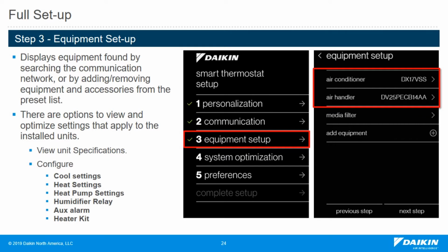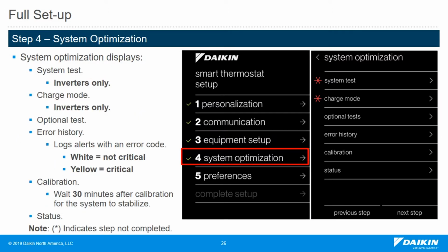Equipment setup tab. This is the one that you may not do immediately, you may return to, but we'll go over all of these. Here's where we'll find our configuration of our cool, heat pump, humidifier, relay connections, heater kits, and all our fine-tuning of our equipment. System optimization. This is done for inverters only. If you're installing a FIT or a 20 or an 18, anything with an inverter, you must run system optimization or you'll get an E11 code. You will have an E11 pop up on the screen and on the outdoor screen as well. And you'll have to allow it to go through the system optimization to remove the E11 code.